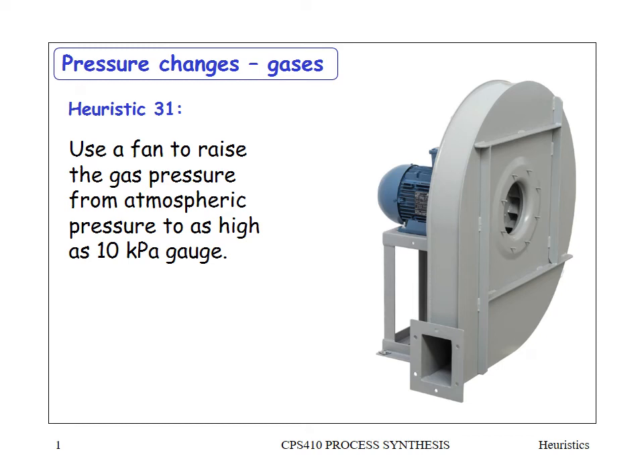In this section we will talk about pressure changes, starting with gases. Heuristic 31 says use a fan to raise the gas pressure from atmospheric pressure to as high as 10 kPa gauge. Generally, whenever you can use a centrifugal fan it's a nice cheap and easy way to move gas rather than compress it. 10 kPa gauge is only about one meter of head, so it is essentially for the lowest pressure applications — just when you want to blow something. The illustrated fan has a large diameter, so it would probably be capable of delivering the full 10 kPa gauge.